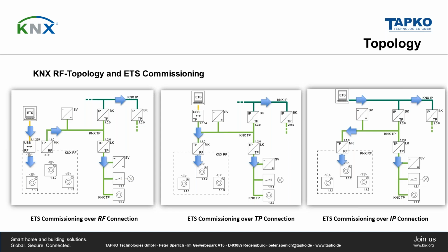The next possibility, in the middle, is that you can use a TP USB interface, and then you can program not only the TP devices that you have connected on your bus, you can also program the KNX RF devices with a media coupler or also over IP. And on the right-hand side, you can program over IP, connected with an IP router to the TP line, and the TP line is connected to RF.